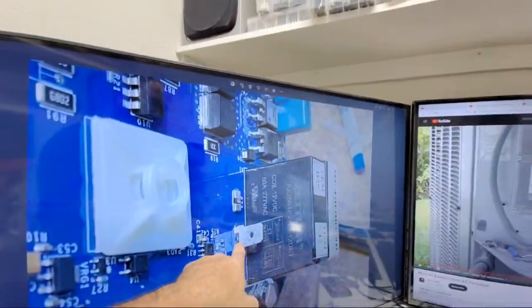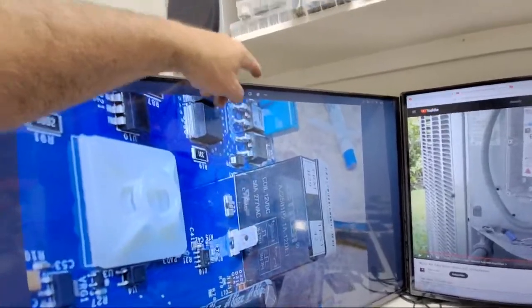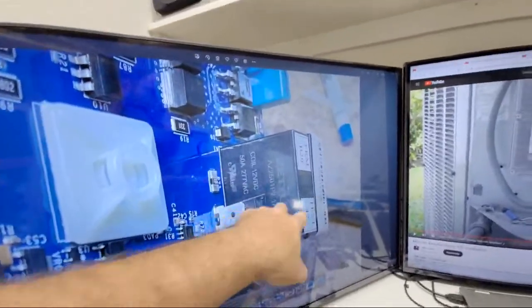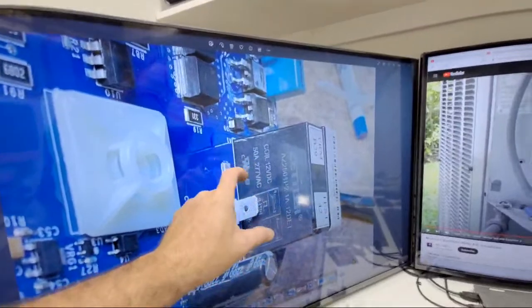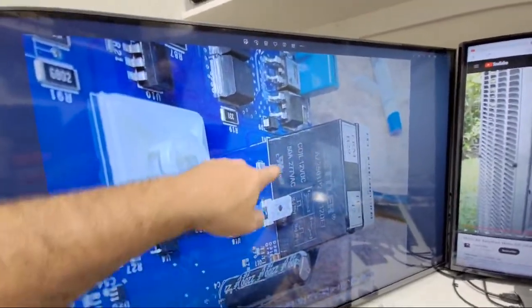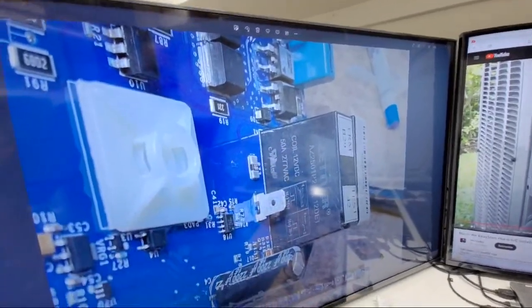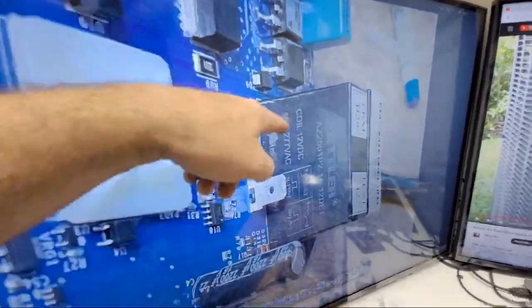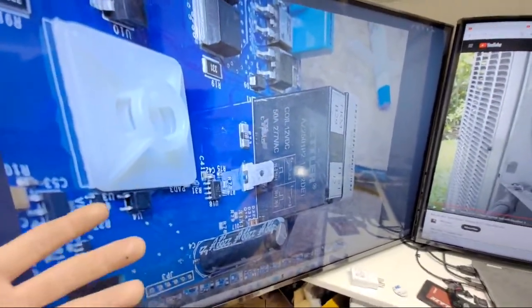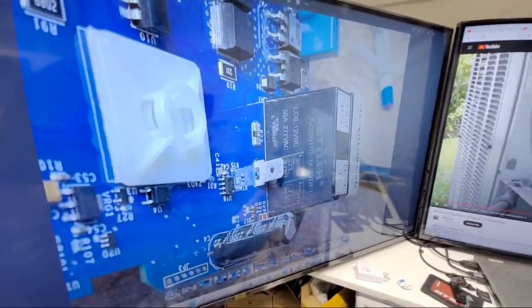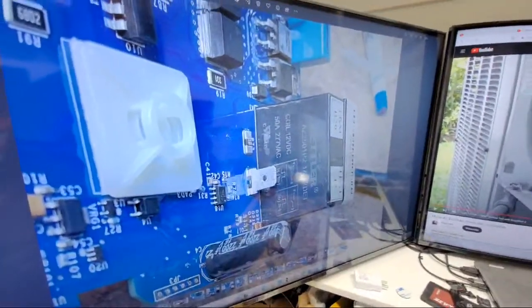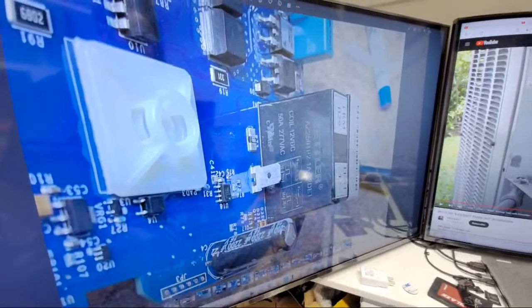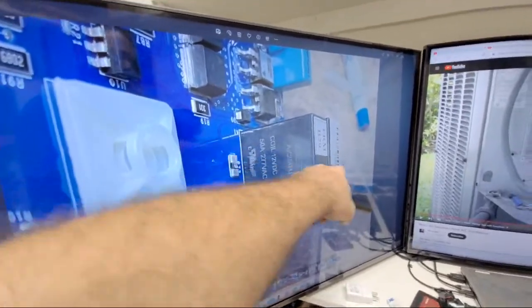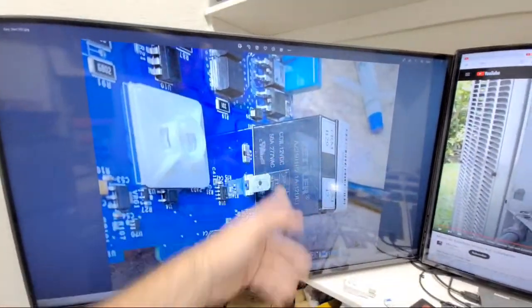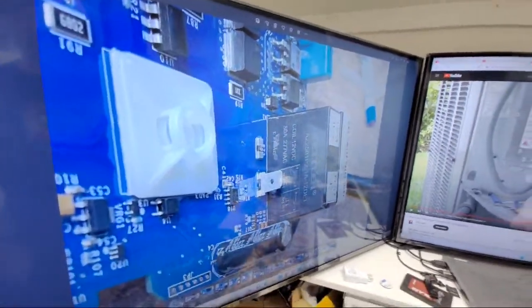After the contactor, you're coming out and going into this thing. Here's an L2, and your run is up above here. It's going through these relays, these little plastic relays. They do say 50 amps at 277, but remember your contactors have locked rotor amp ratings for when it clicks. So even if these are in parallel, those little contacts aren't comparable to a compressor contactor.